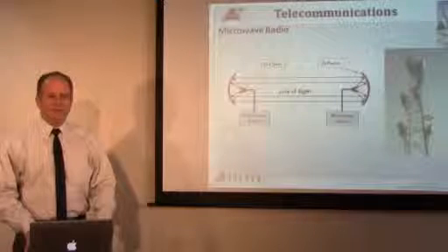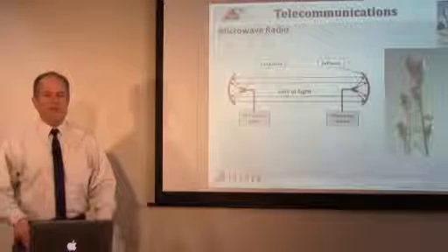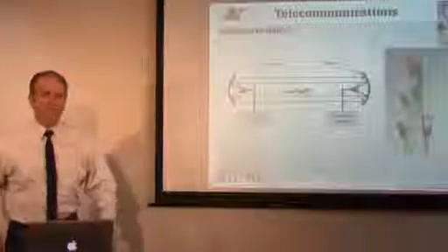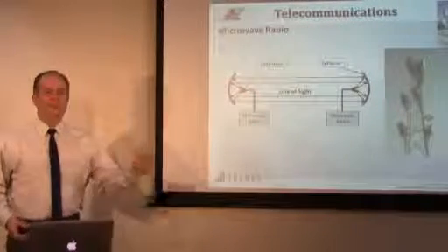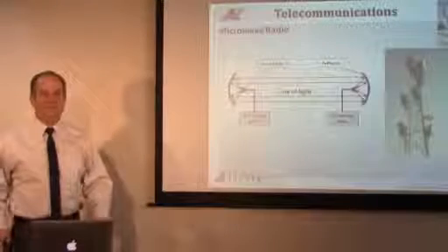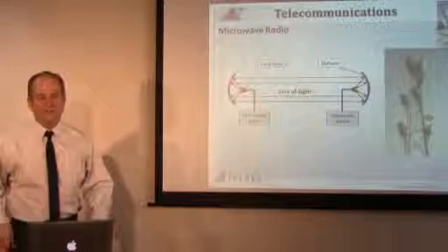But newer digital microwave systems are in use today because resync time after a microwave outage is fast enough to be used in protective relaying. So you're using microwave for the voice and the data, the protective relaying, the SCADA, call centers, company information, and those types of things. So that's microwave.